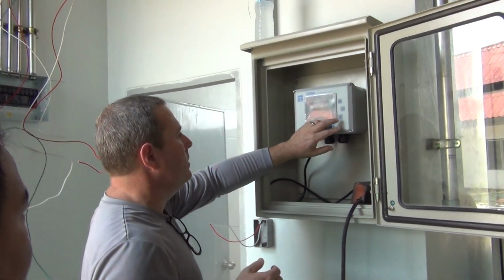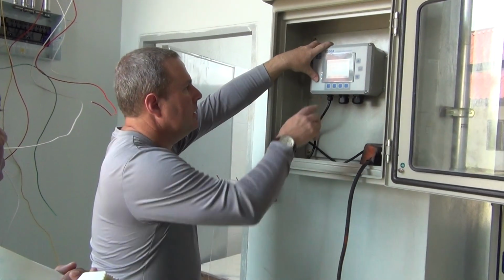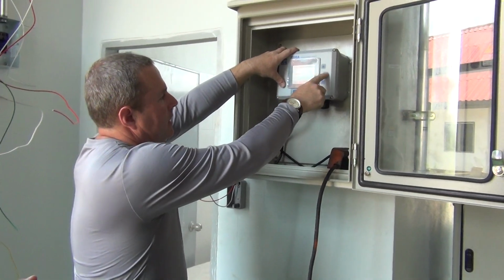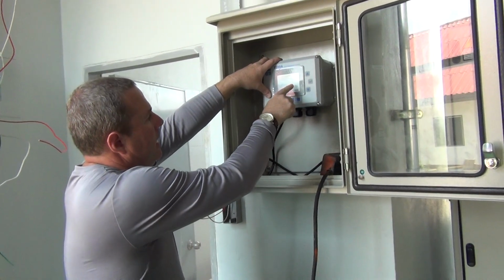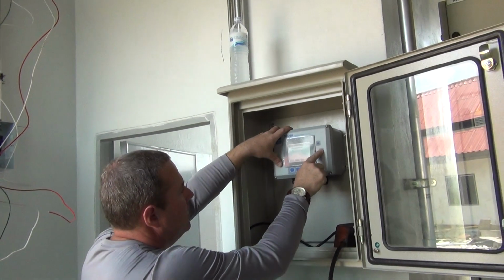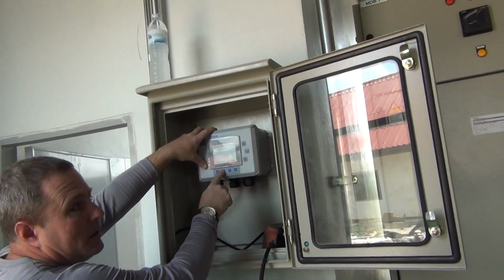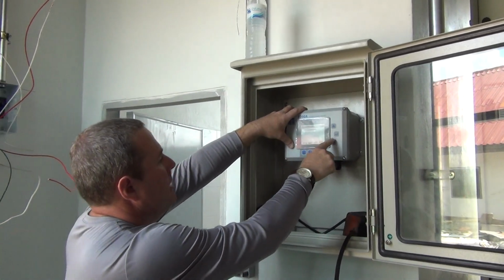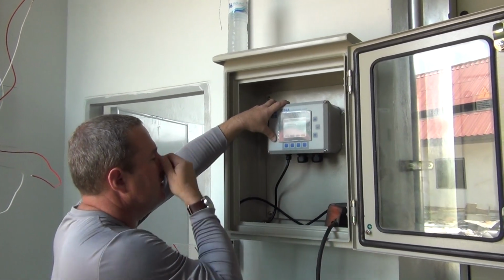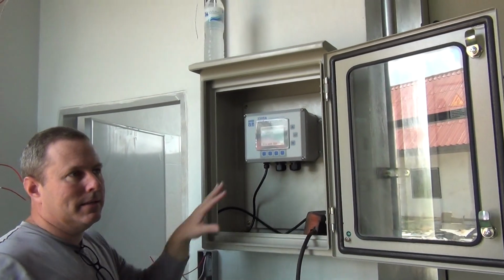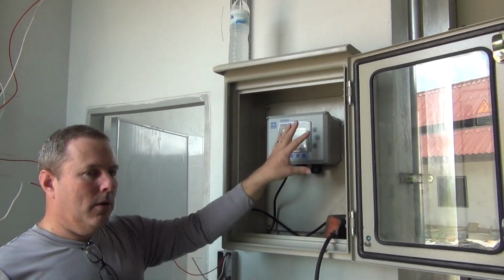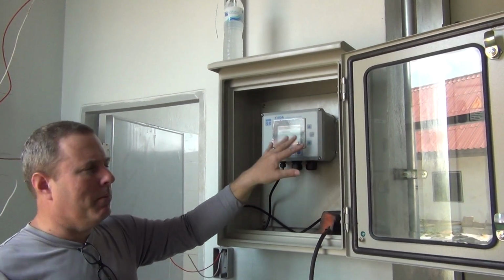So what I will do, I'm going to press enter, and where it says relay disabled, I'm going to select this, and I'm going to first select the general alarm, and I'm going to enable. And then it says instrument. Well, we don't have any, this is not part of a network of these. We could have 256 per network, but we don't.